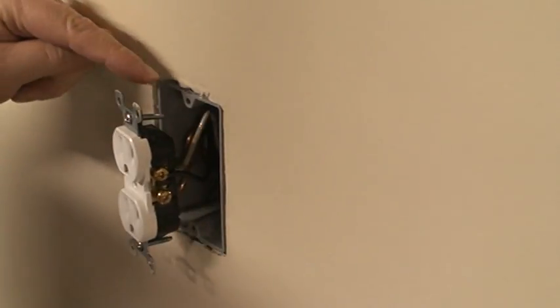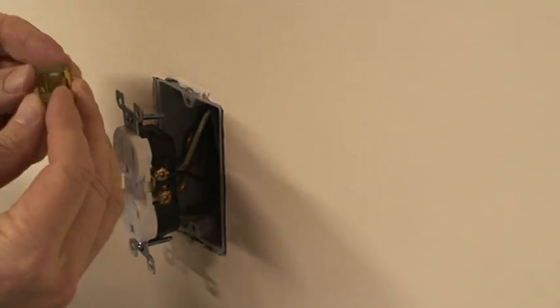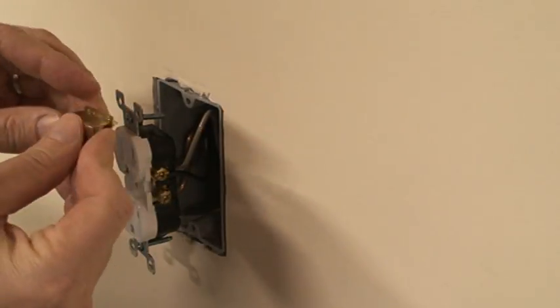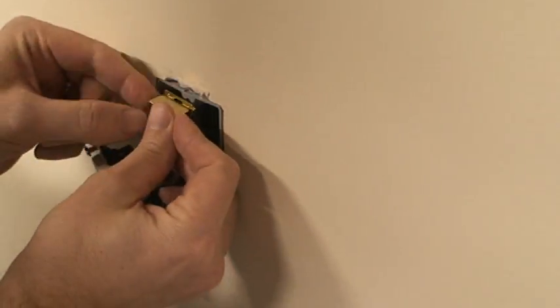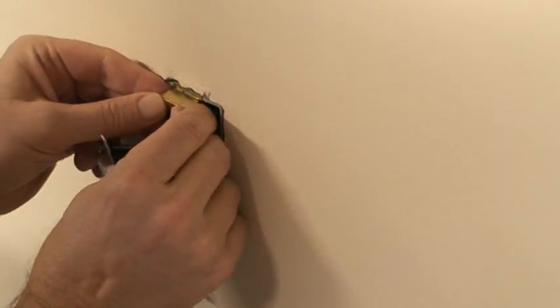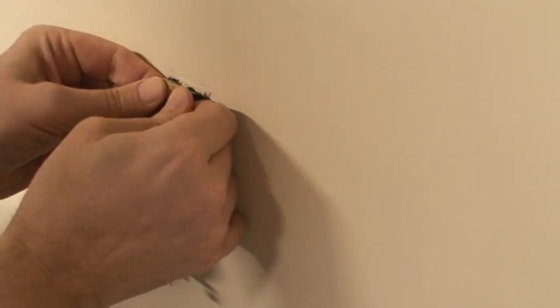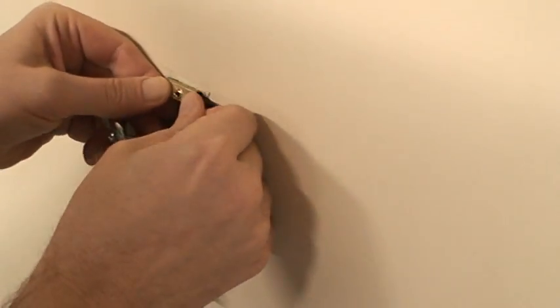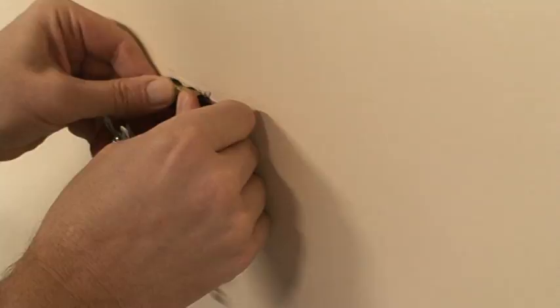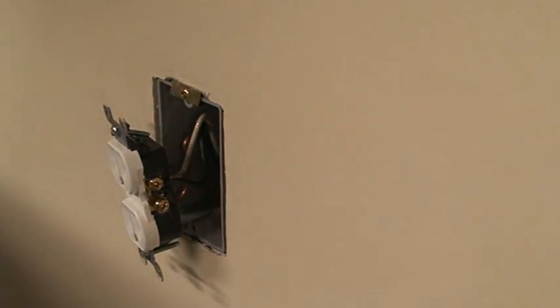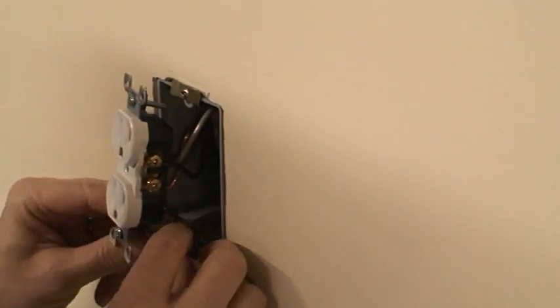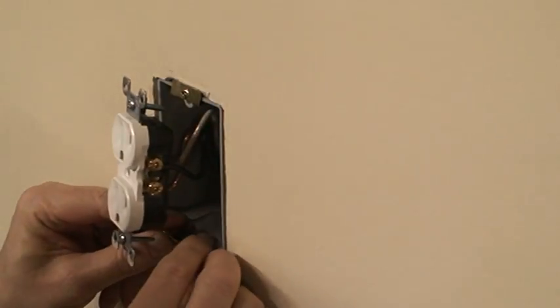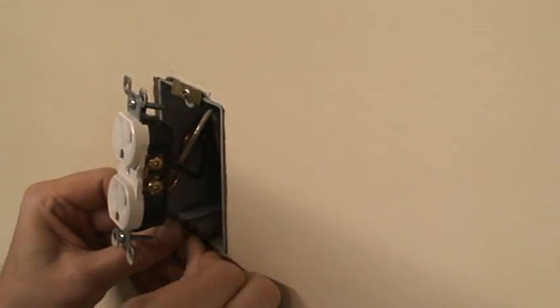So what we're going to do is pull this away from the box and install a G-clip over this point and a G-clip over this point. I'll rotate the G-clip with the two legs facing downwards, I'll line it up over the hole in the box and push it onto the box, and I'll take a second G-clip and line it up over the lower hole and push it onto the box.